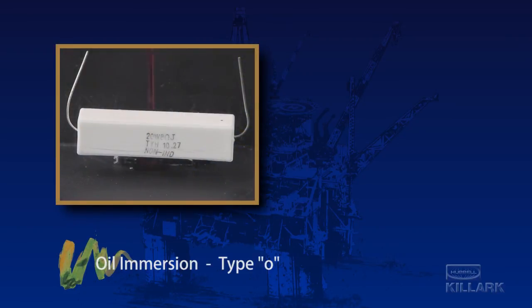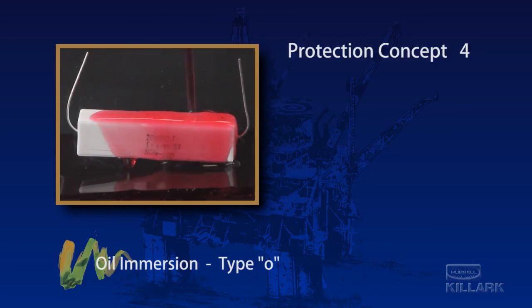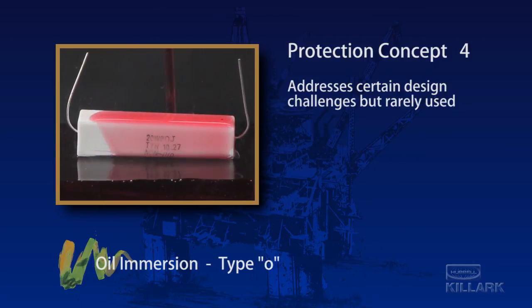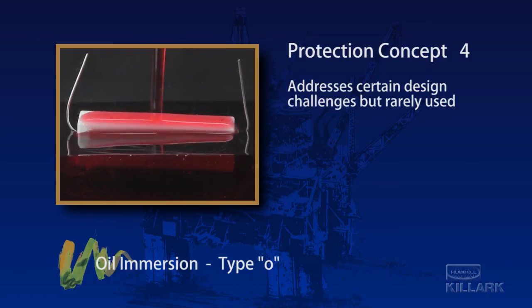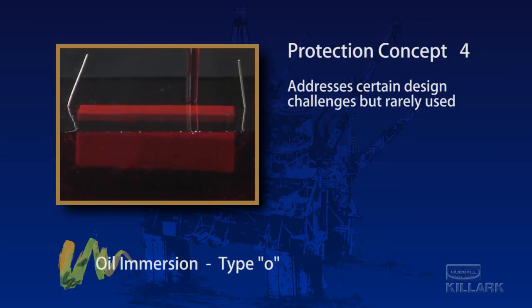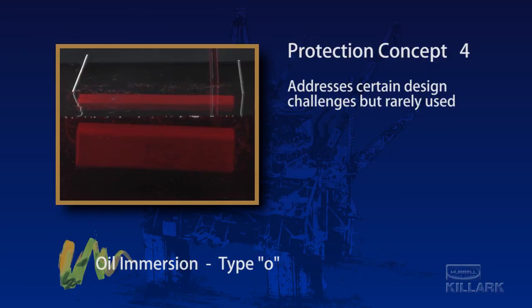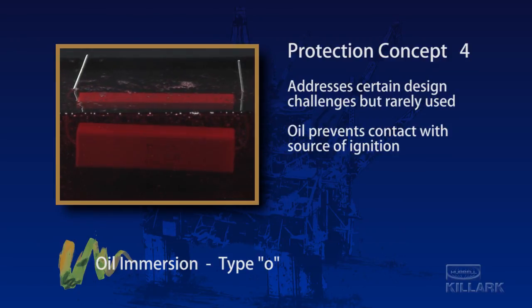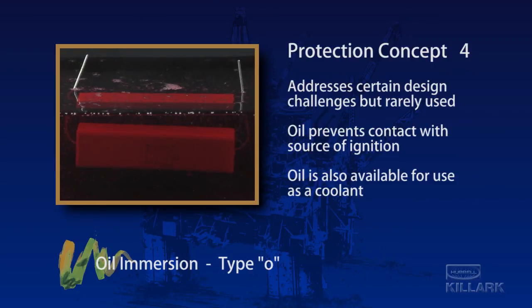An additional technique within this concept is oil immersion, Type O. Although a rarely used type of protection, there are some pieces of equipment that may present challenges that can be more easily overcome by using non-flammable oils to submerge the apparatus. The oil surrounding the device prevents the hazardous material from coming into contact with the source of ignition. It may also be called upon for cooling. Transformers and other static devices, as well as certain startup equipment, could employ oil immersion.